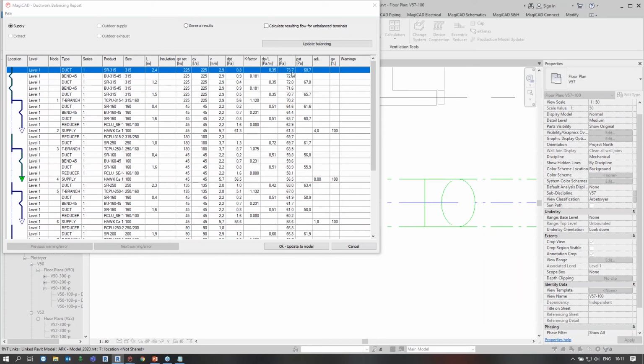So now the total pressure needed from the fan is 73.7, it was over 220 something before. So in the long run it's much more economical to buy - maybe it's a little more expensive to buy bigger ducts, but the energy to put into the fan is less. Okay, update the model.